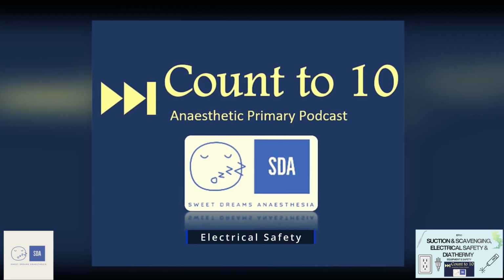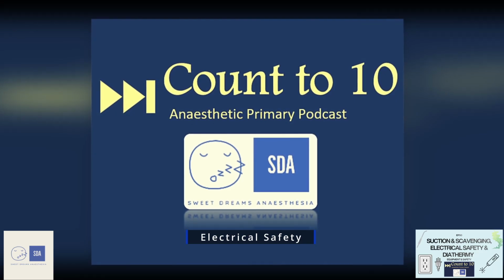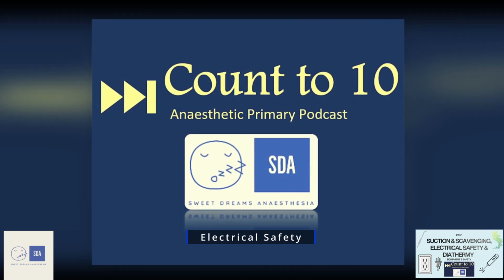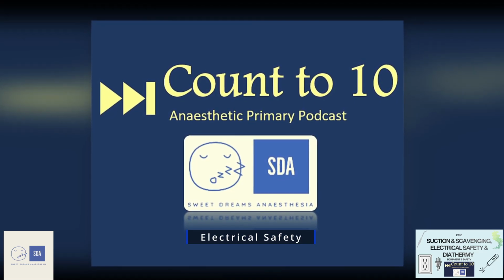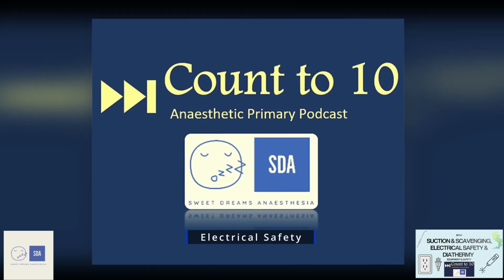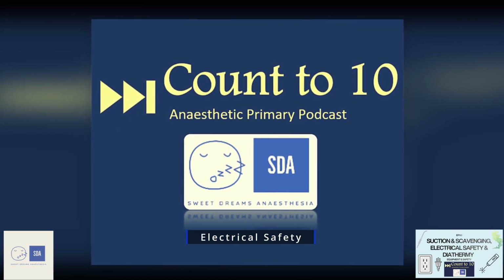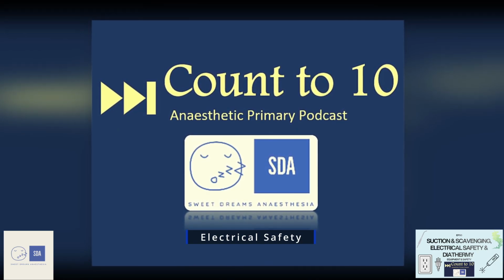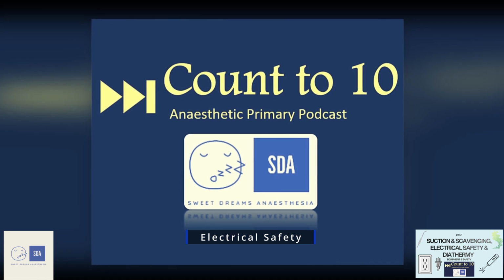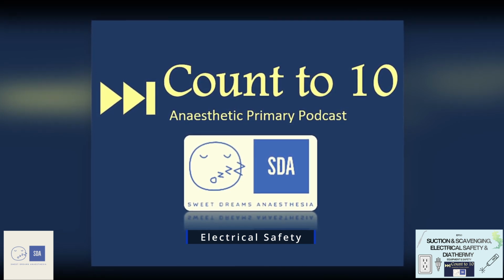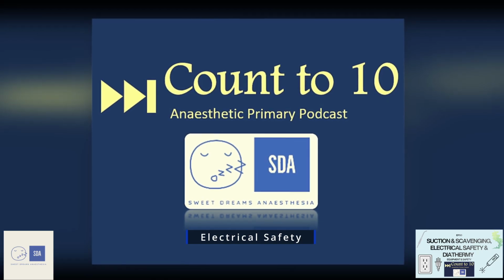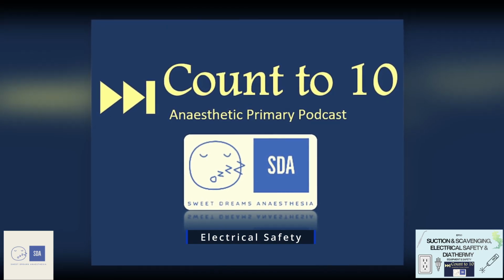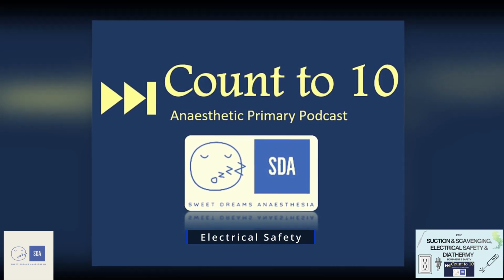The reason you want LIM systems along with RCDs is because LIMs will allow you to continue using that power equipment without it shutting off abruptly, because certain things you don't want to shut off abruptly, like your ventilator. So this gives you a chance to notice that there's a problem and then figure out whatever way you want to then fix it or stop using that equipment.